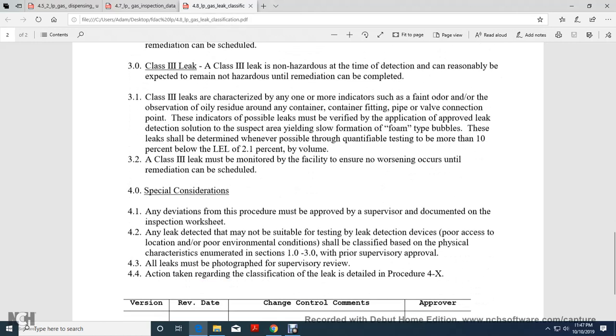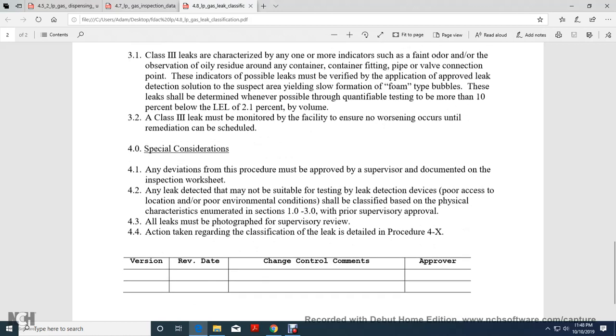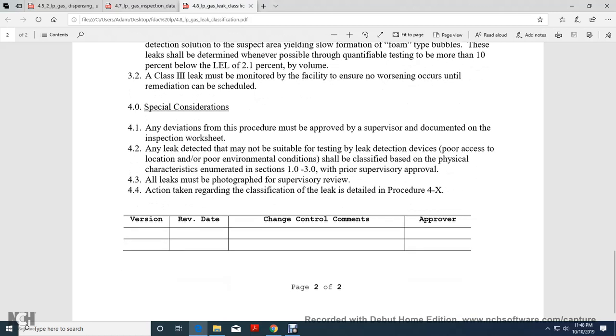Class 3 leaks: A Class 3 leak is non-hazardous at the time of detection and can reasonably be expected to remain non-hazardous until remediation can be completed. Class 3 leaks are characterized by one or more indicators such as faint odor or observation of oily residue around any container, pipe, or valve connection point. Indicators of possible leaks must be verified using an application-approved leak detection solution, yielding slow-forming foam-type bubbles. Leaks shall be determined whenever possible with quantifiable testing showing more than 10% of the low explosive limit of 2.1% by volume. Class 3 leaks must be monitored by the facility to ensure no worsening occurs before remediation can be scheduled.